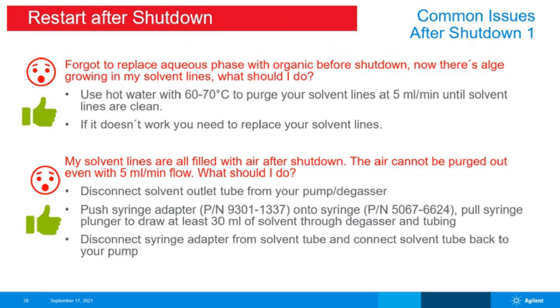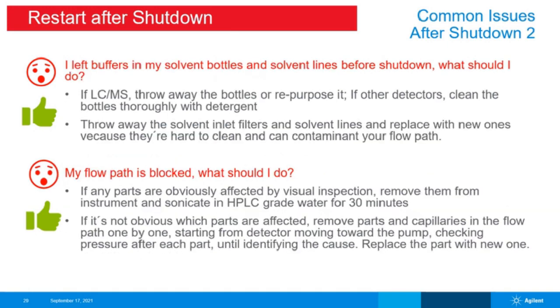In the next two slides, you can find some common issues after a shutdown and how to overcome them or which solution best fits. We see here that most of the common issues are related to the mobile phase, algae in the mobile phase, air in the flow path. And here on the second slide, things which are going in the direction of crystallization in the flow paths which are blocked. So principally flow path issues are the most common problems you can have with an LC system when you turn it on after a longer time off.